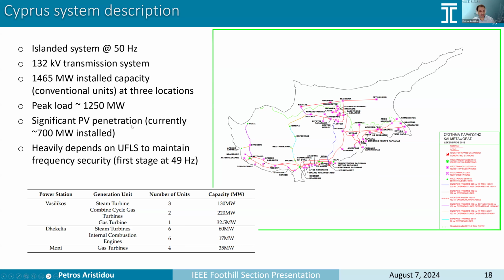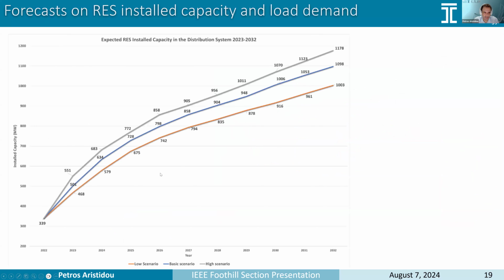This is in the Mediterranean, there is lots of sun, and currently there are around 700 megawatt installed capacity in PV systems. Around 300 of them are rooftop PVs, and the rest are commercial PVs installed in different areas. You can see here that this is half of the installed capacity of the conventional generators. So there is a significant amount of PV penetration, and there is also wind that I have not included here. At this point, the island heavily depends on under-frequency load shedding schemes in order to maintain the frequency security.